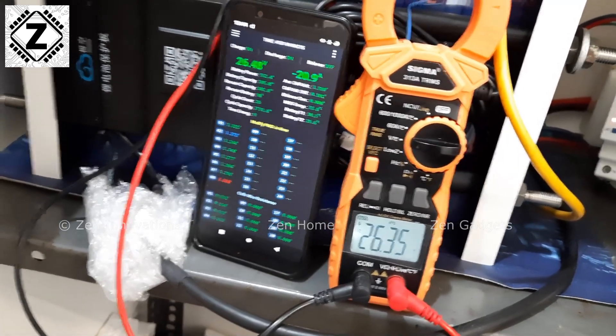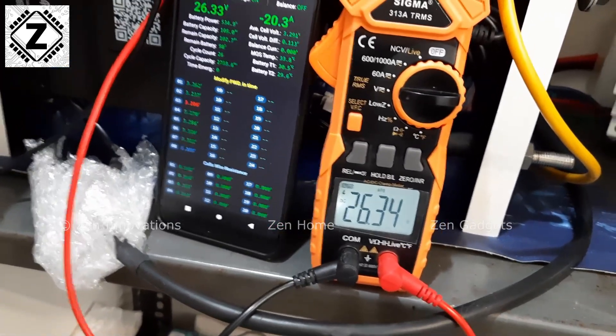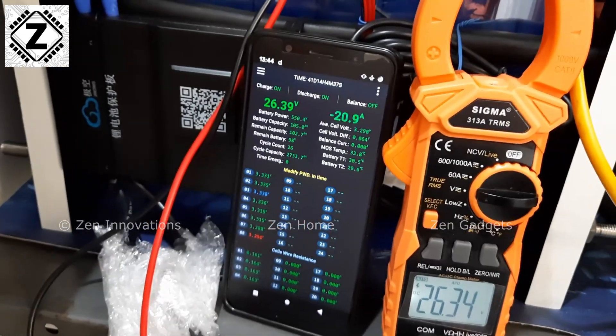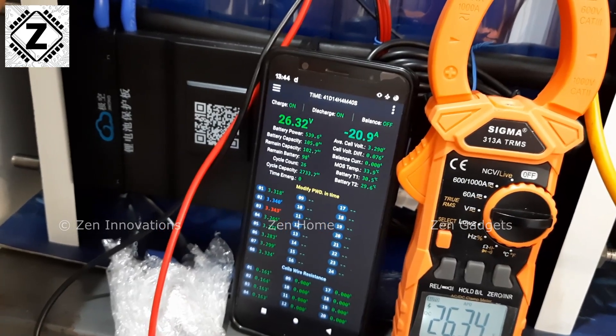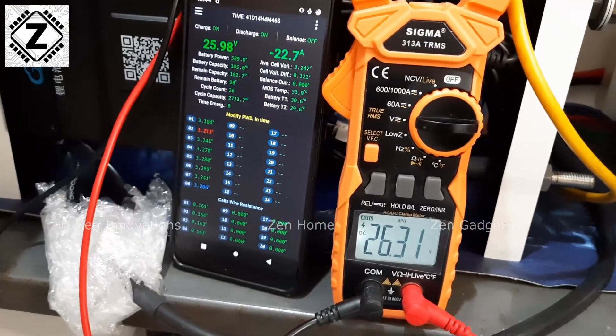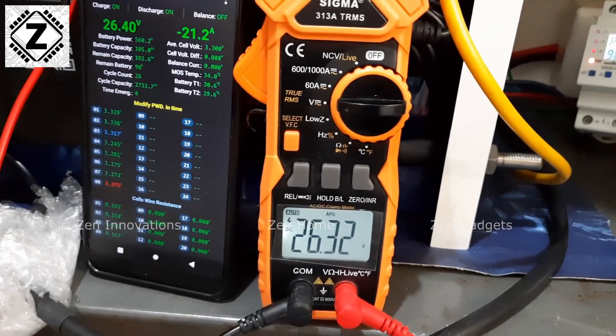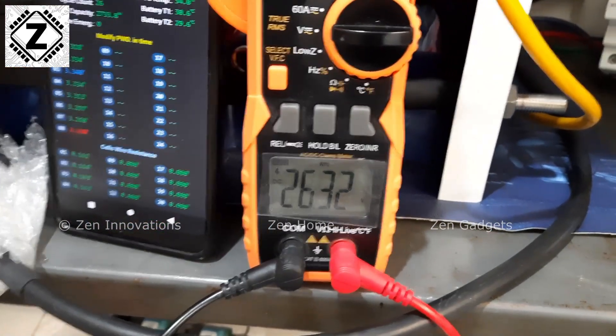To confirm this, I have my Sigma 313A clamp meter connected and as you can see there is absolutely no fluctuation on that readout. But the BMS is jumping all over the place — 26.2, 26.3, 26.4, then back down. On the clamp meter it is practically rock solid at 26.3 volts.